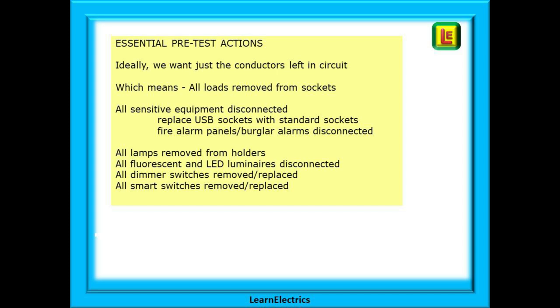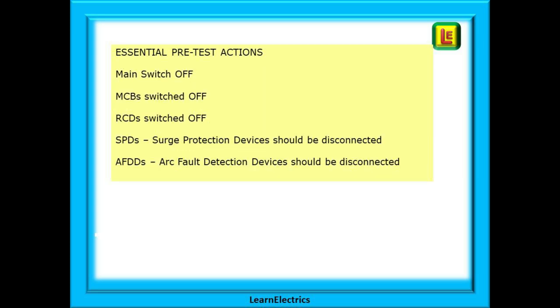This is all part of the testing setup and part of our job. If testing a whole property, the main switch must be off. All MCBs should be switched off so that they do not get secondary current paths. Turn all RCDs to off to prevent damage to them. SPDs — surge protective devices — are the same; they should be disconnected to prevent damage. And AFDDs, or arc fault detection devices, should also be disconnected for the same reasons.